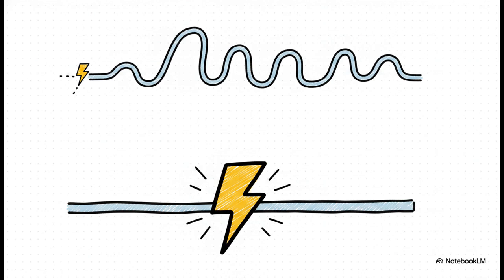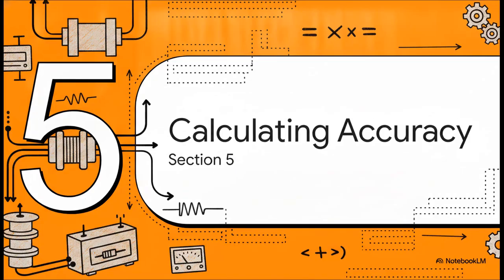Why? Well, it's just physics. Lower current traveling over a long run means lower I²R resistive burden losses in the copper wiring itself. By choosing 1 amp, you easily maintain your measurement accuracy over that long distance. Now, 5 amp CTs are still great, but they are traditionally preferred for shorter runs where those burden losses just don't add up enough to cause problems. And finally, Part 5, calculating true accuracy.